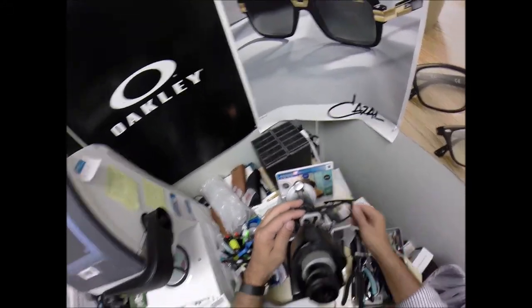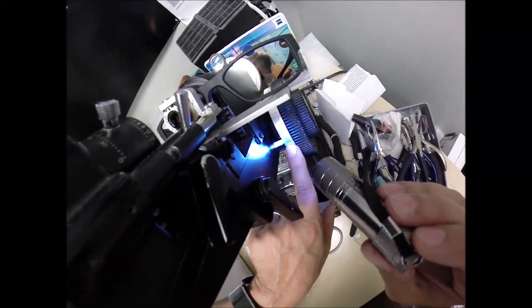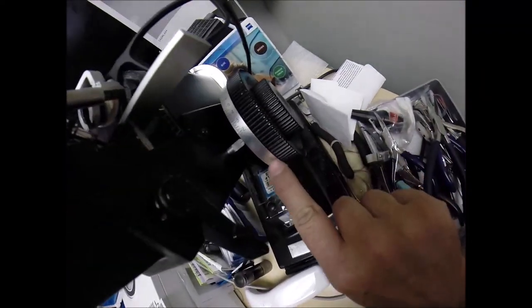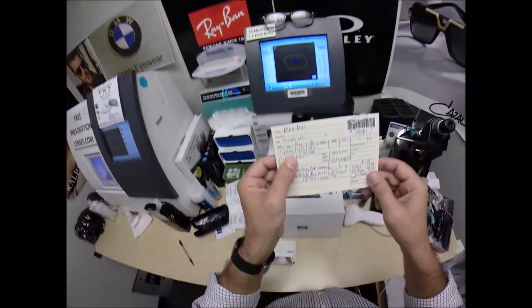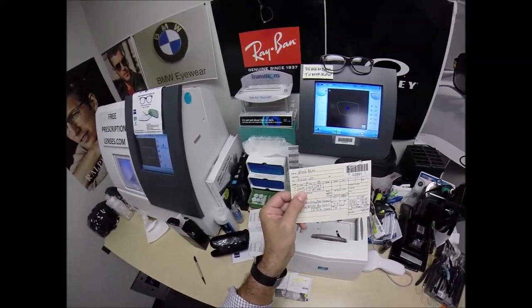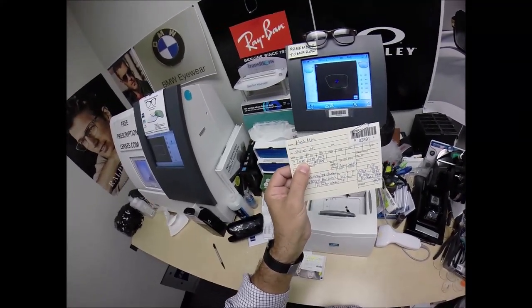Ooh, almost nailed it. Read the power. And I am getting plus 125, one tick mark past one, going towards two. And the pluses, the black pluses. See the plus sign, not the red minuses, the black pluses. Ooh, there's thunder outside. So, the unit of measurement we use is called a diopter, spelled D-I-O-P-T-E-R. Starts at zero and goes up in quarter increments. So you're on the fifth rung of a ladder. 0.25, 0.50, 0.75, one, one and a quarter is the fifth rung.